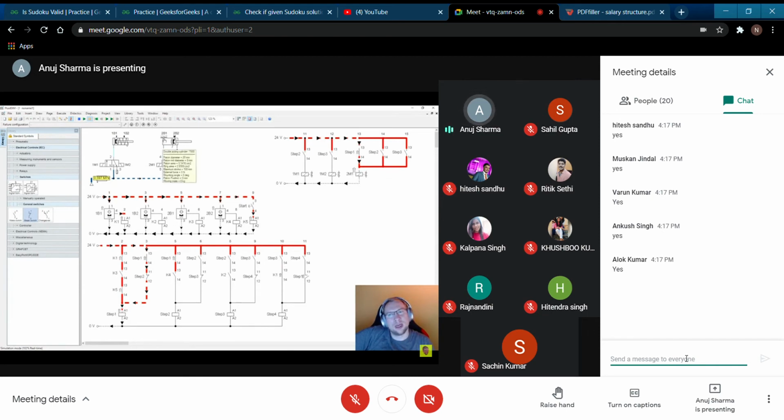2M1 is active, activating the cylinder here, extending. That's good. Next thing that will happen, 2B2 will come active, right? 2B2 is connected to K4. K4 will close, activating step 2. Step 2 will close this one here, will keep 2M1 active, will close this one here, will activate 1M1. So let's see. 1M1 active, 2M1 also active. There we go. 1M1 is active, meaning cylinder 1 should extend here. There we go. Should start extending.